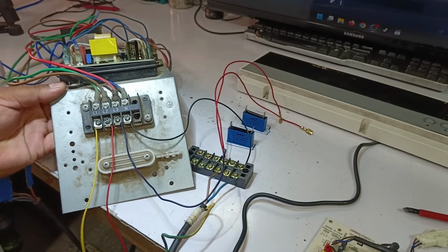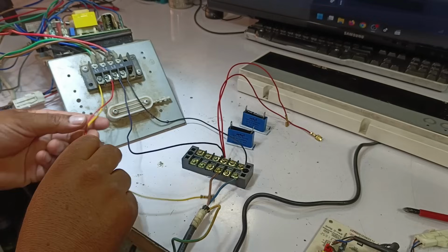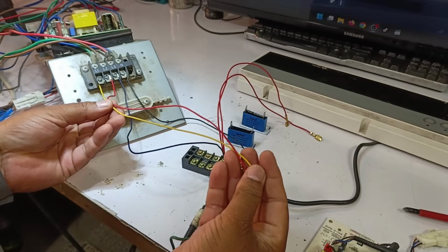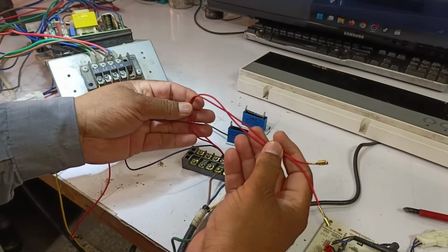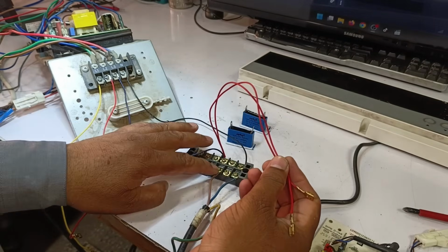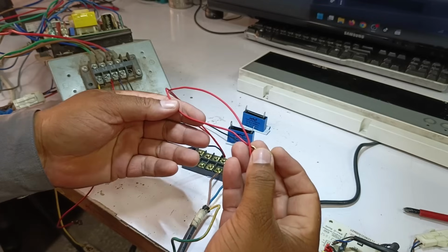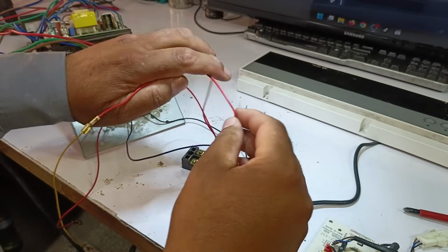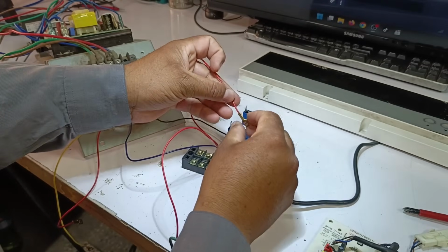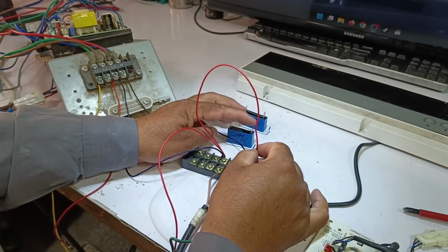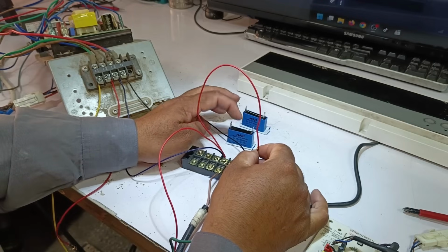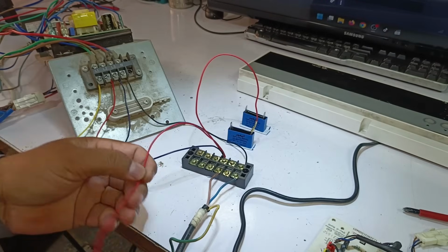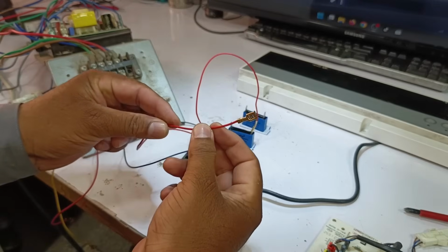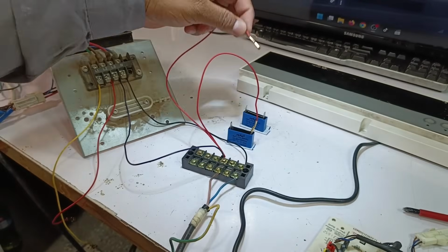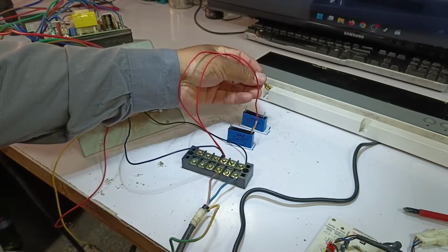Now, we have two connections remaining here, L1 and L2, which are the yellow and red wires. We also have the 2 points that are connected to the single-phase supply. Now, from the main single-phase supply, we will take one wire. We will connect this wire to either side of the first capacitor. We have already prepared the proper system for this. So, I will connect it to the right side connector of the capacitor. The second remaining wire from the single-phase supply will also be connected to the right side connector of the second capacitor.